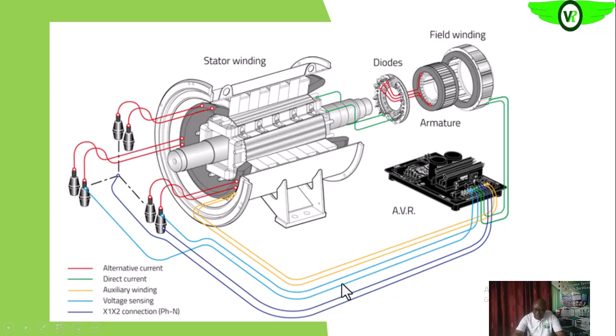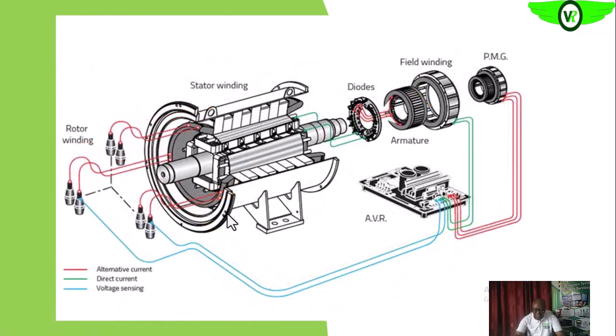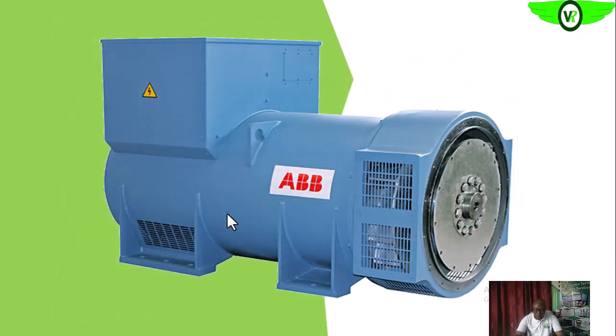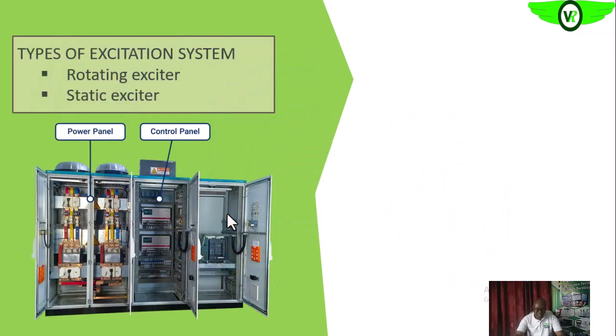Then it is taken to your AVR, then from your AVR to your exciter field. The exciter field is magnetized and induces voltage onto the exciter armature, which will now be fed onto the rectifier bridge that will convert the AC produced here to DC that will be fed into the main feed. So the main field will now produce a magnetic field that will induce into the main armature and give us the output that we actually want. So everything put together is what we have here. So that's for the rotating exciter.